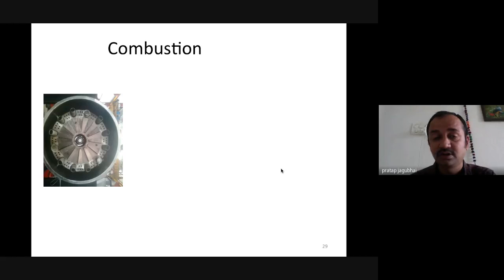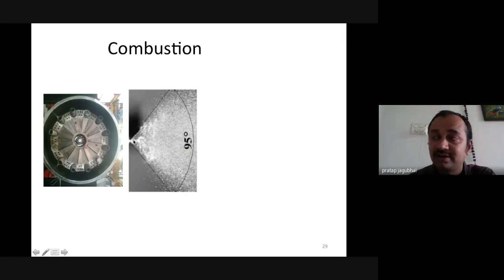So what to do? For that, we need to have 3 T's. The first T is temperature. You can see this is the flame nozzle, which is put inside the burner. This is an oil and gas fired boiler. This is the atomizer. If you ignite, the fuel gets spread from here, and when ignited with the air, the combustion starts. When fuel burns with the air and is ignited, the fuel particle that catches fire releases heat and mixes with another particle, and this way the complete flame gets stabilized.